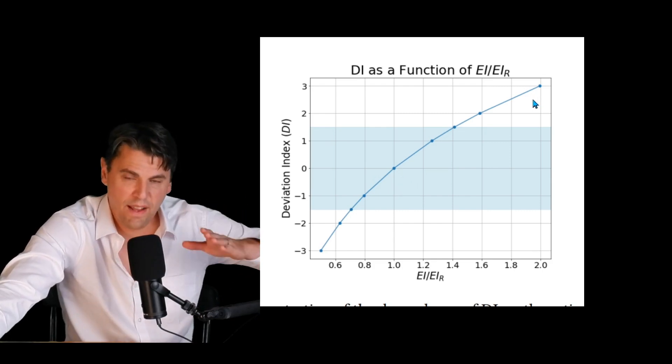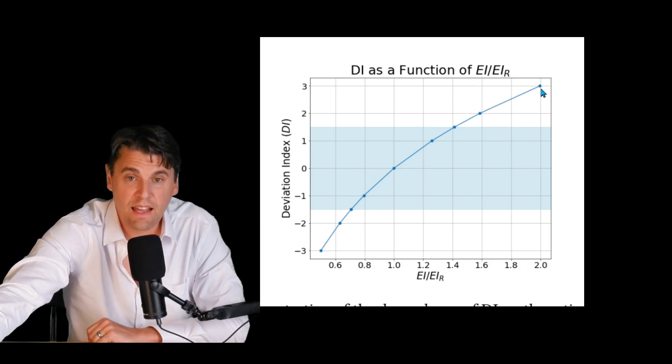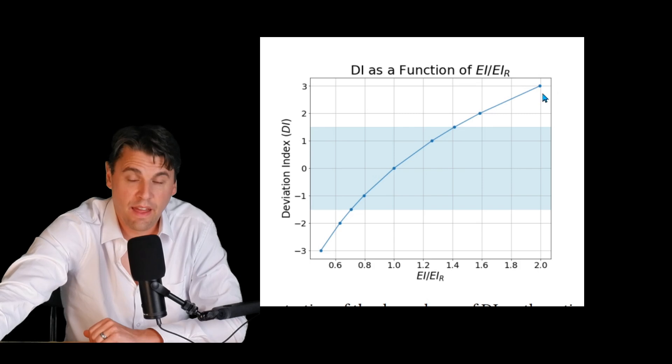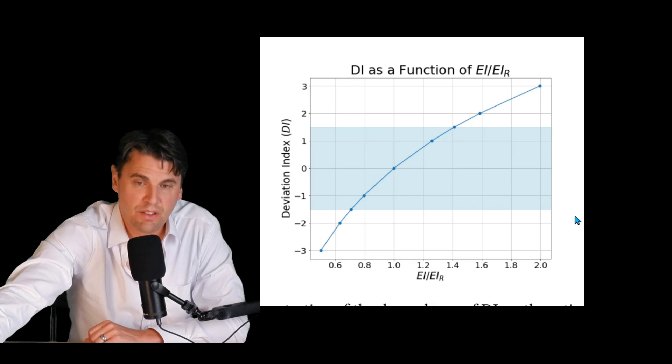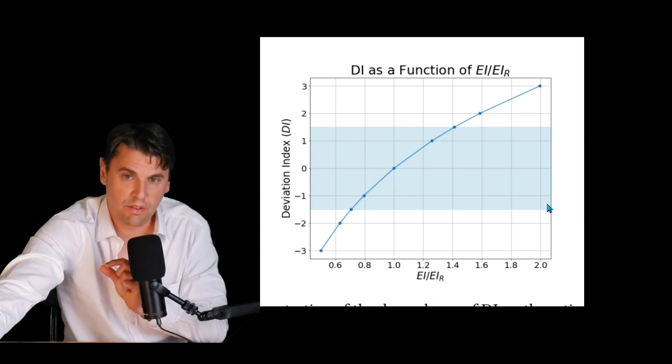Then for instance, if you had twice as much exposure on the image receptor as you were hoping or planning to do with that target or reference, then you actually would have a deviation index of three. Likewise, if you had half as much exposure as you were targeting, you would have a deviation index of minus three. The idea is with the deviation index, you'd like to stay as close as possible to the planning and get the deviation index smaller.